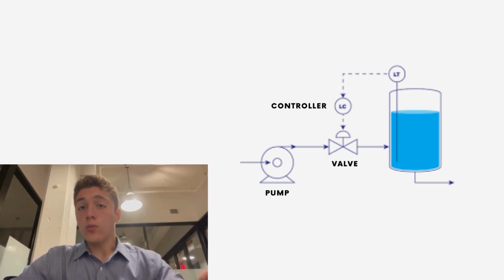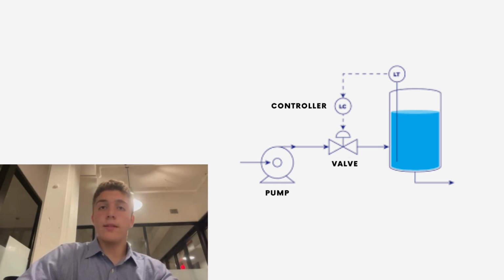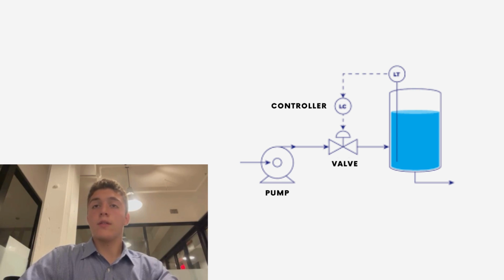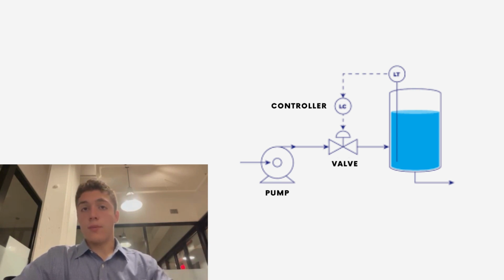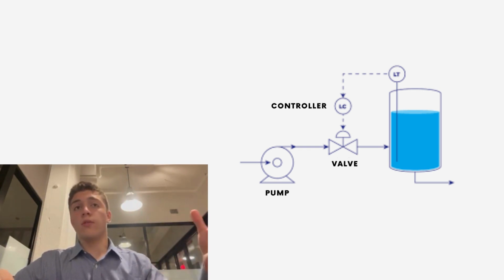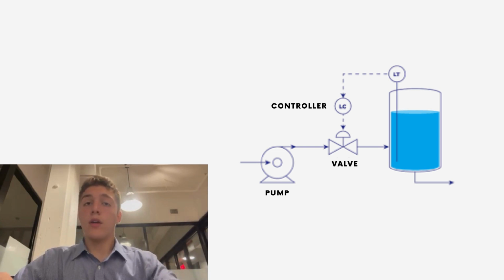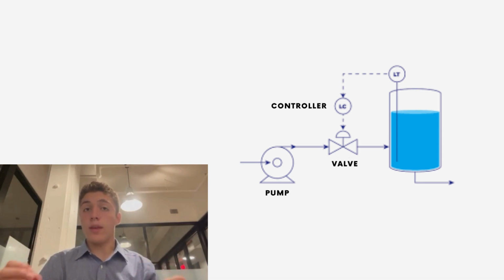One important tool is a loop object, which uses a PID controller to regulate a piece of equipment. So hypothetically, let's say a water pump, as an example, is filling up a vat, which is being drained, so that the vat is at 50 gallons constantly. The loop uses a set point or desired value and a controlled variable or the current value. So the set point would be the 50 gallon mark, and the controlled value would be whatever it is currently. Therefore, we need the water to flow at different rates at different times in order to make sure that the level stays the same.